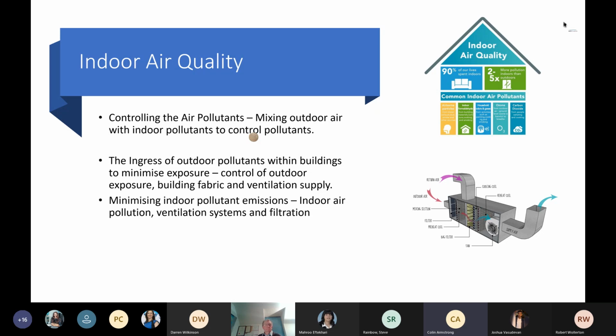I've just touched on the air intake positions. There is recommended guidance, which includes that intakes need to be placed away from direct impact of short-range pollutant sources, such as roads, especially if they're within a few metres of a building. Inlets for mechanical systems can be placed on the roof to avoid ground-based pollutant sources, if there are no other sources present at high level. Quite often we'll go on top of a building and someone will have put an intake next to a kitchen extract or a toilet extract. So there needs to be consideration when people are putting the inlets on the roof from the air handling units. And Rob touched on the filtration.